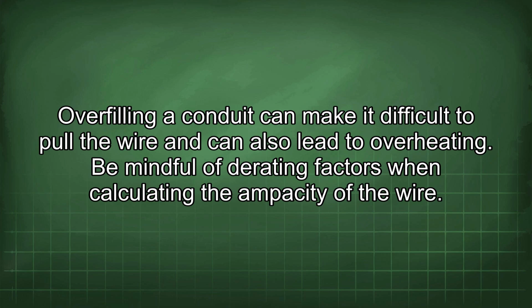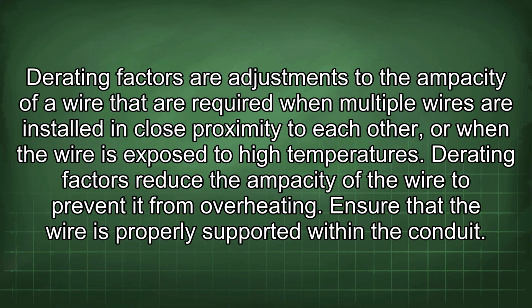Be mindful of derating factors when calculating the ampacity of the wire. Derating factors are adjustments to the ampacity of a wire that are required when multiple wires are installed in close proximity to each other, or when the wire is exposed to high temperatures. Derating factors reduce the ampacity of the wire to prevent it from overheating.